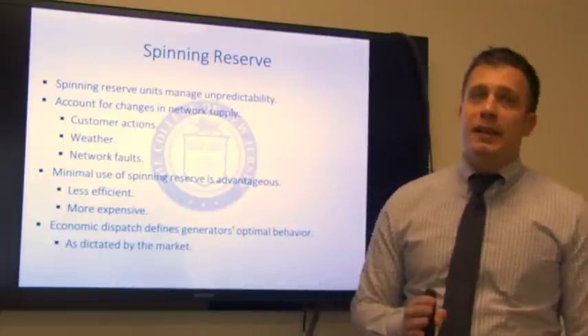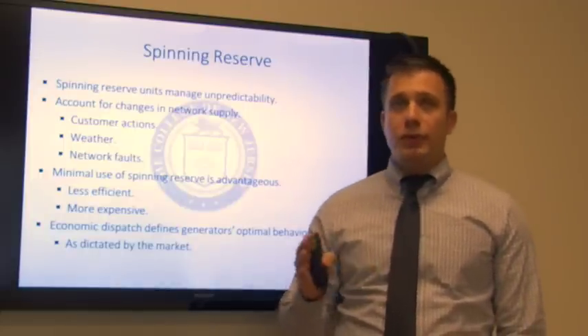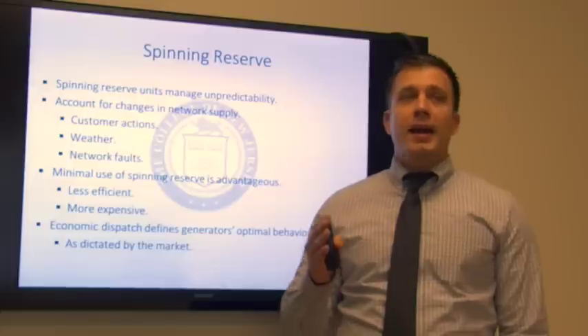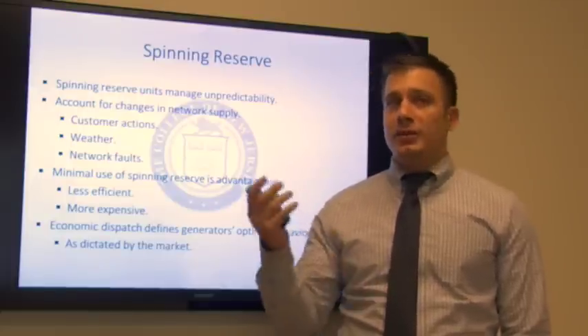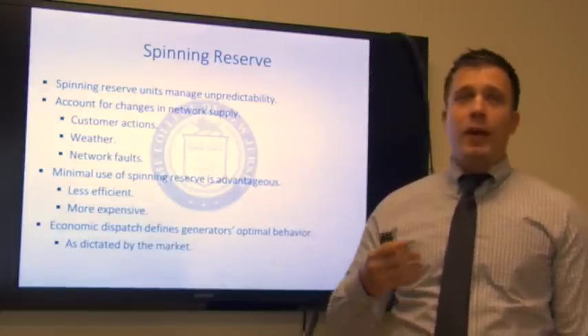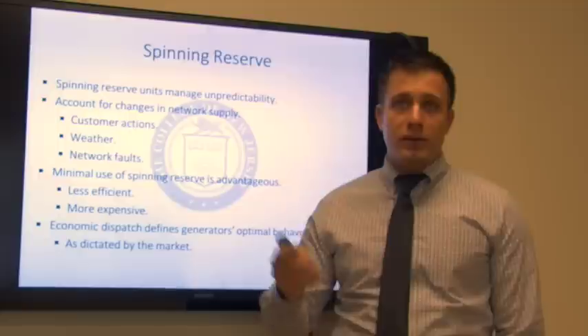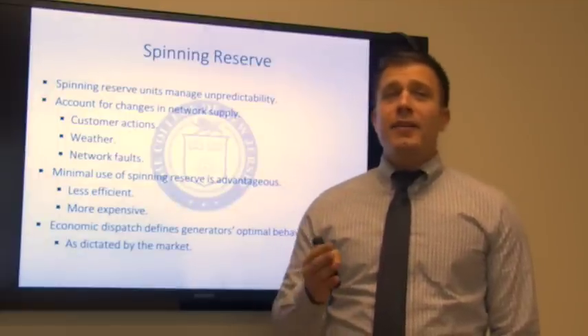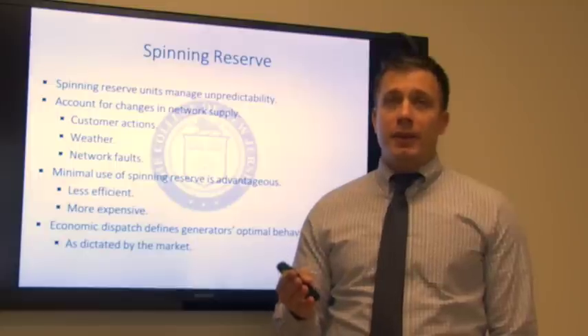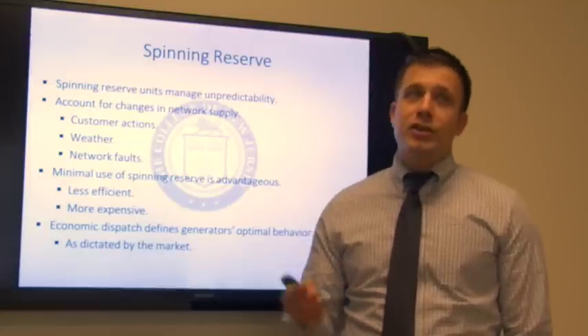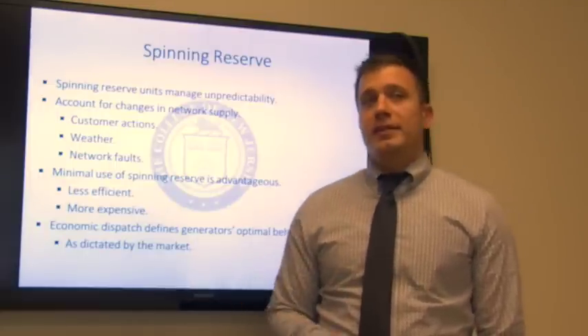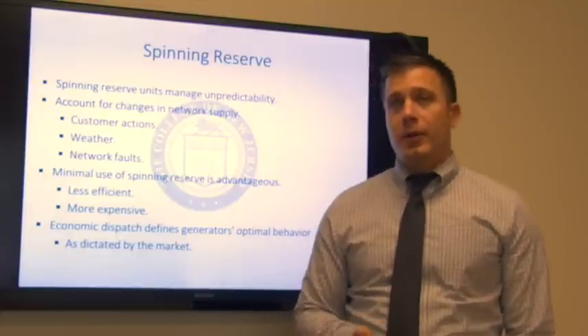These units must be dispatched to account for unpredictable changes in network supply as well as demand, resulting from customer actions, weather, and things like network faults. However, it's advantageous to minimize reliance on spinning reserve units because, on average, they're less efficient and more expensive to operate than their traditional counterparts.